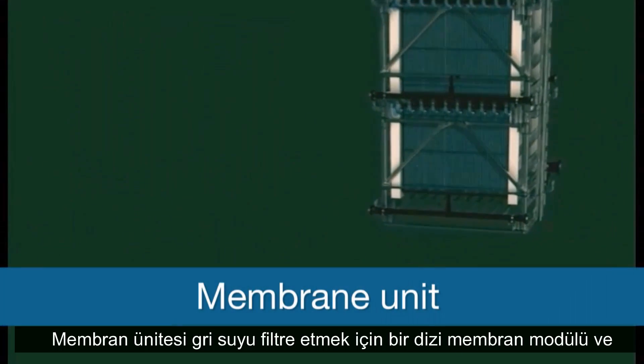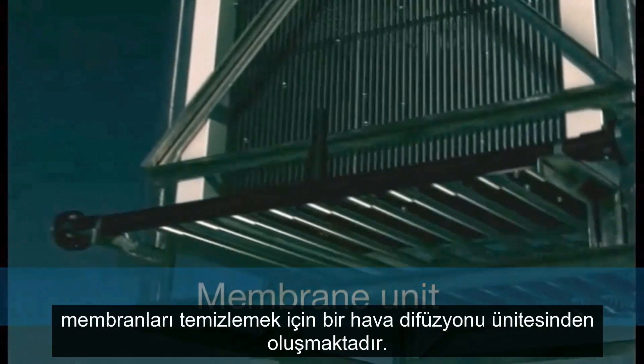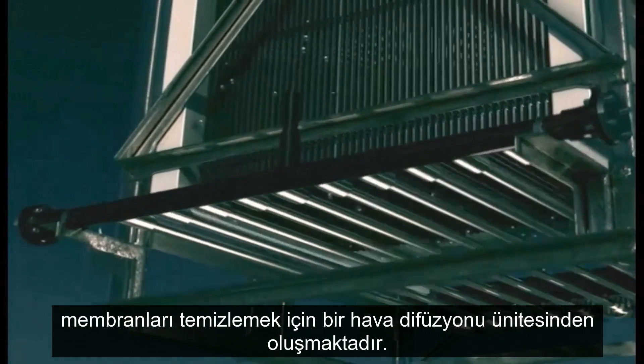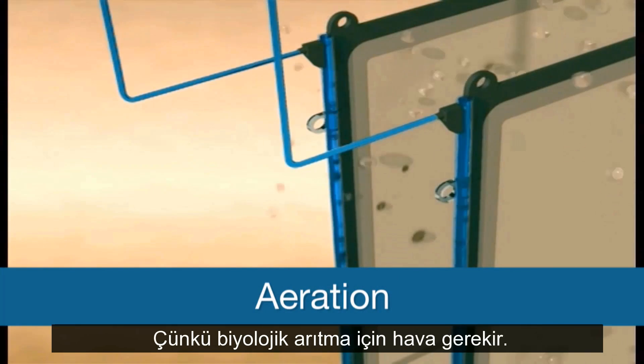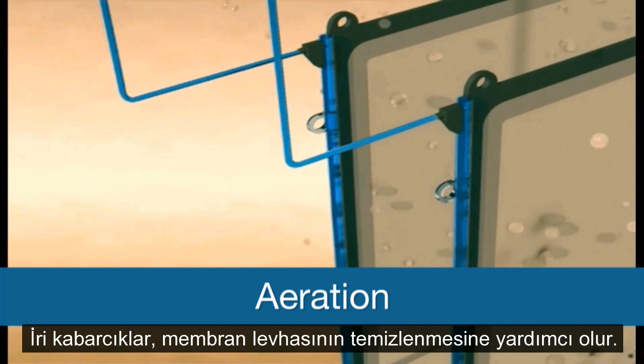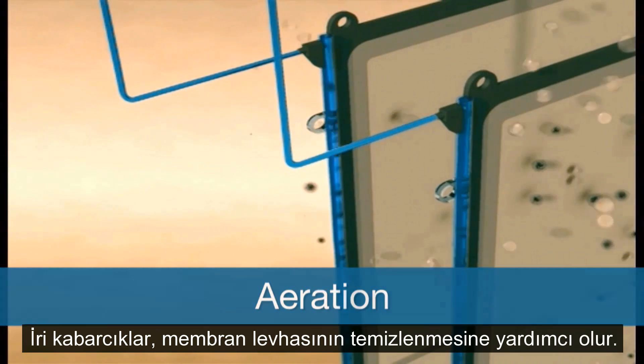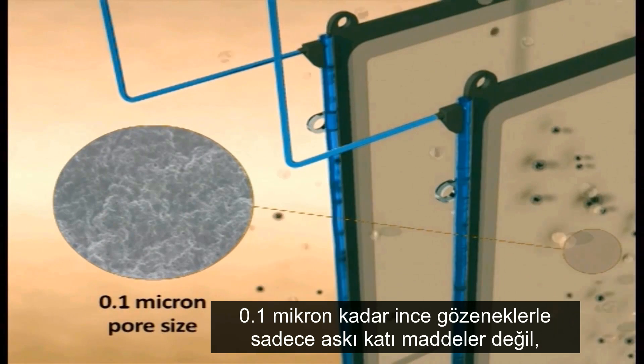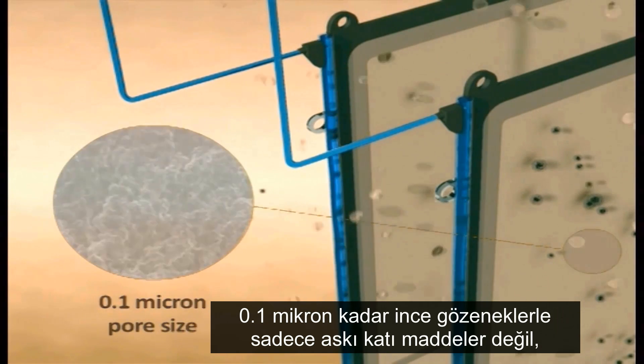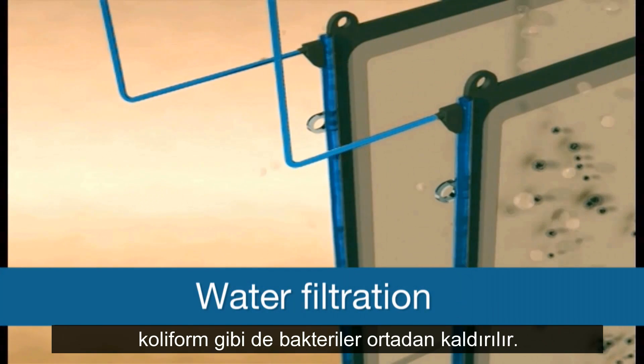The membrane unit consists of a series of membrane modules for filtering the grey water, and an air diffusing unit for cleaning the membranes. Aeration takes place from the bottom of the tank because air is needed for biological treatment. Coarse bubbles help to clean the membrane sheet.